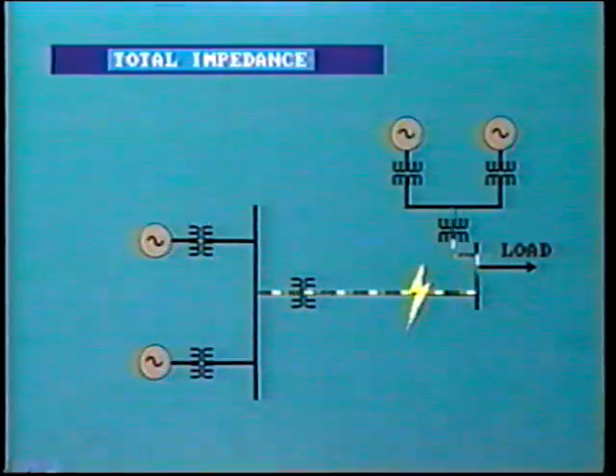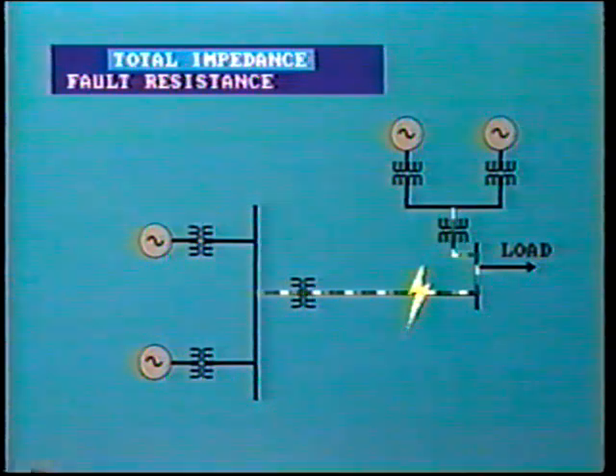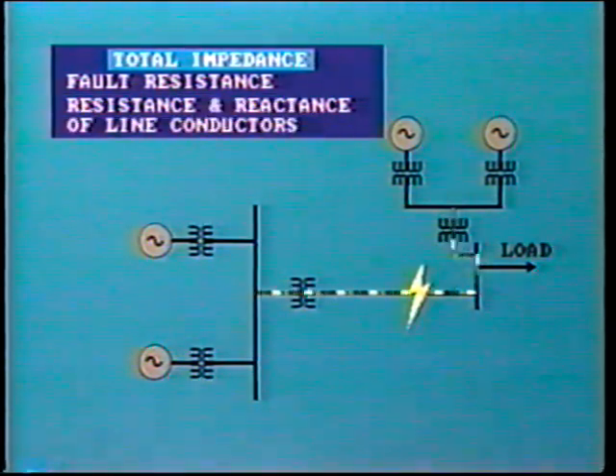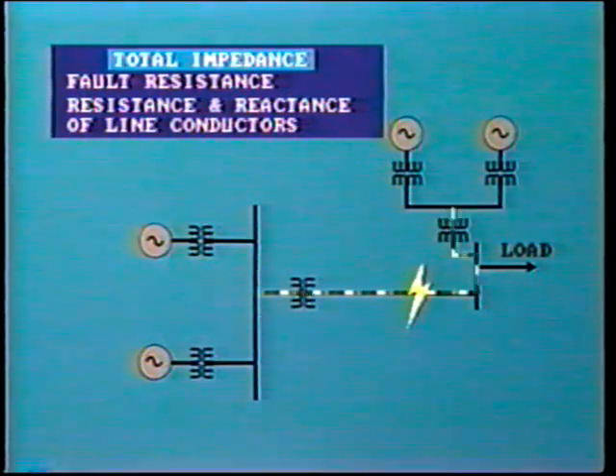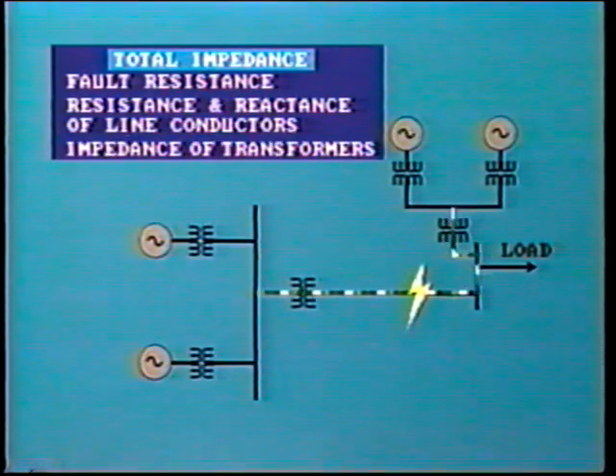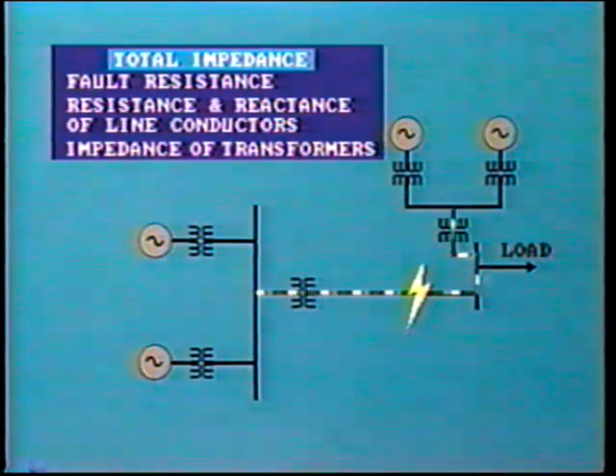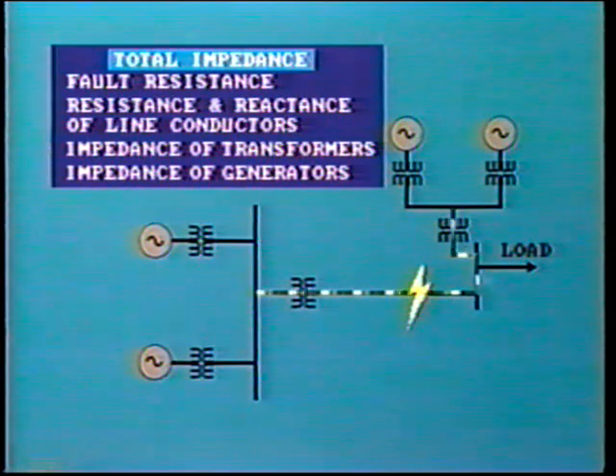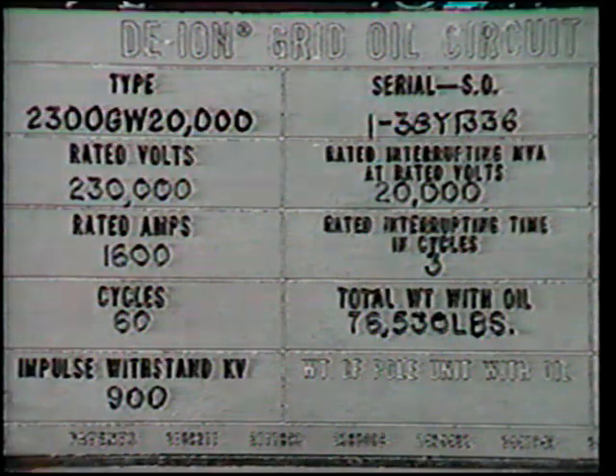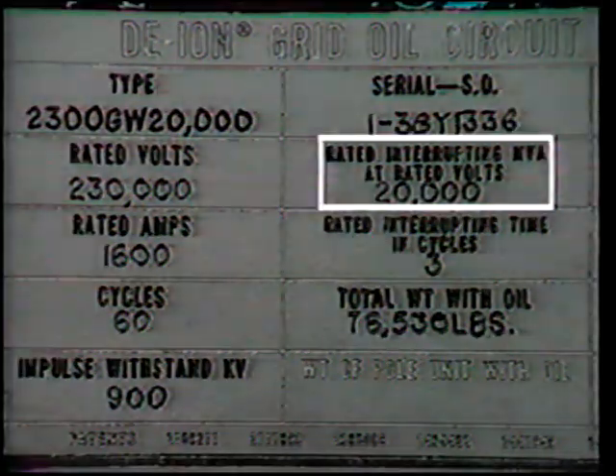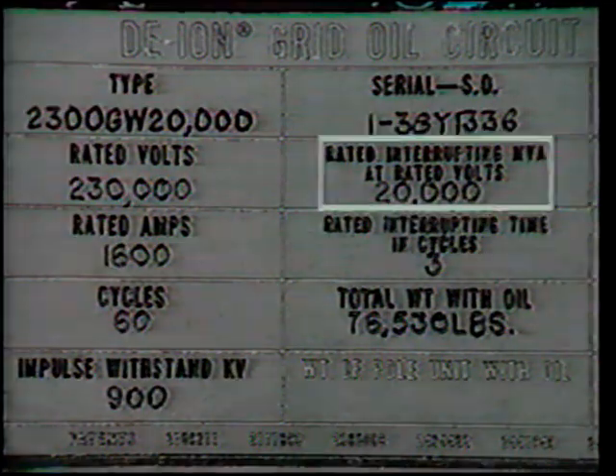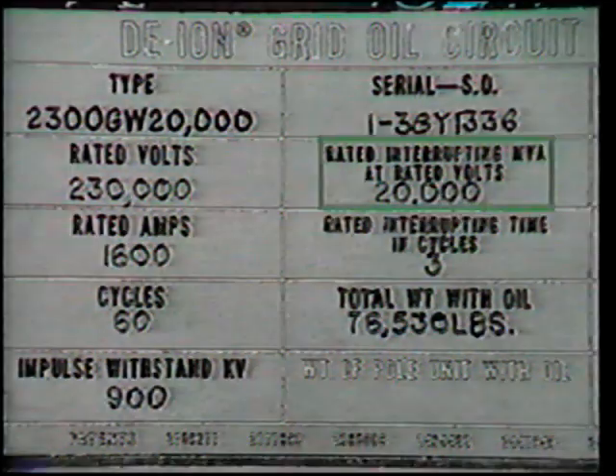The total impedance is made up of A, resistance of the fault itself, B, resistance and reactance, that is, impedance of the line conductors, C, impedance of any transformers or reactors in the circuit, and D, impedance of the generating source. The calculation of probable fault currents for different conditions is a very important task for the system designer. Now, why is this? Well, any switchgear which is installed must be capable of handling the fault current. If a breaker is undersized, it could be completely destroyed when trying to clear a heavy fault current.